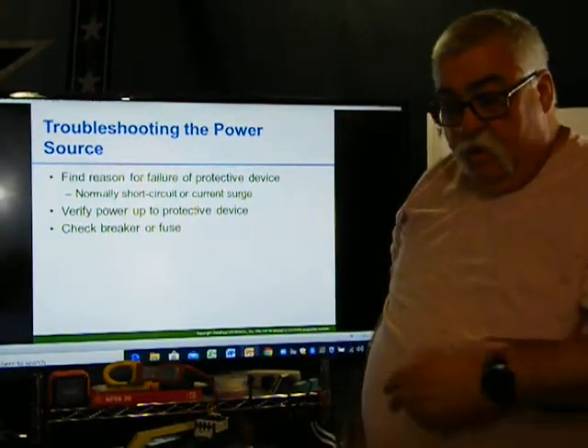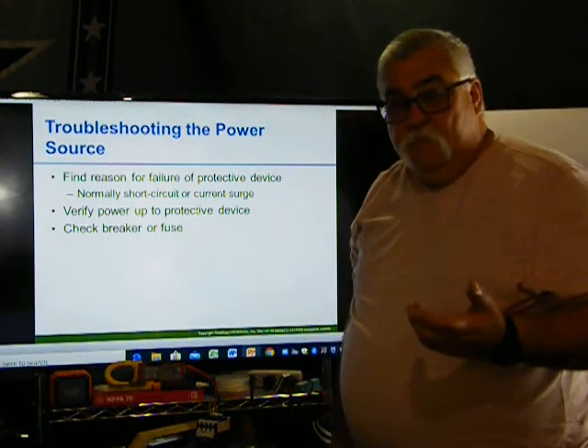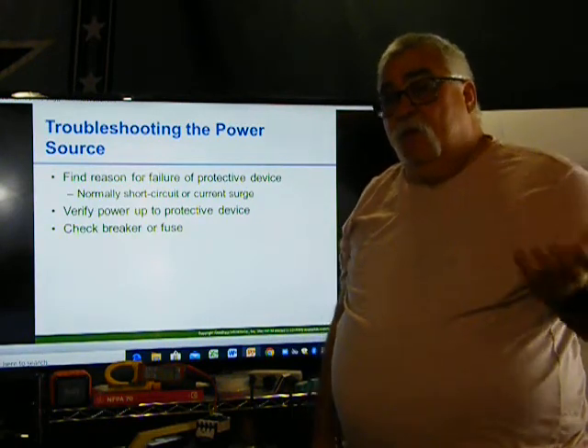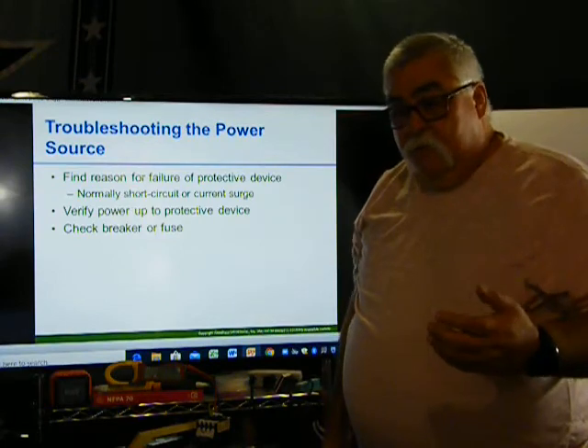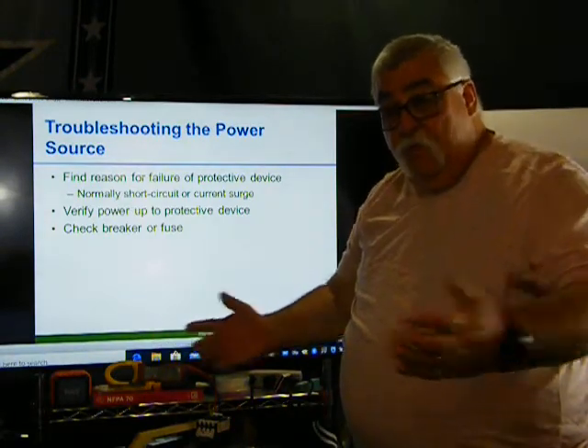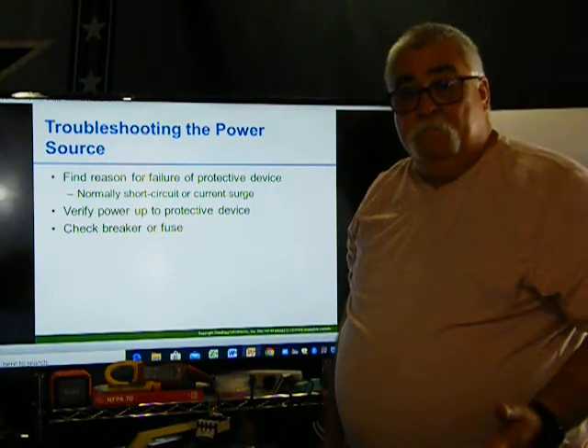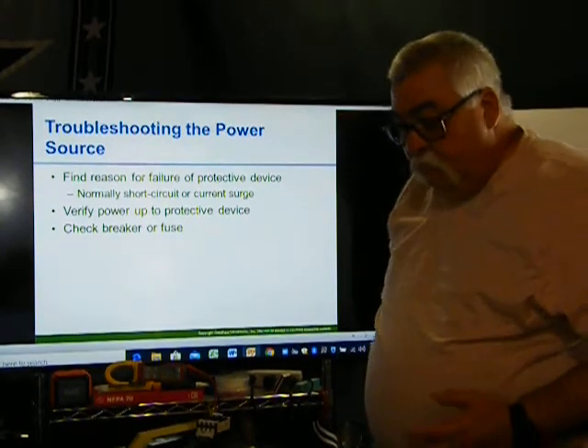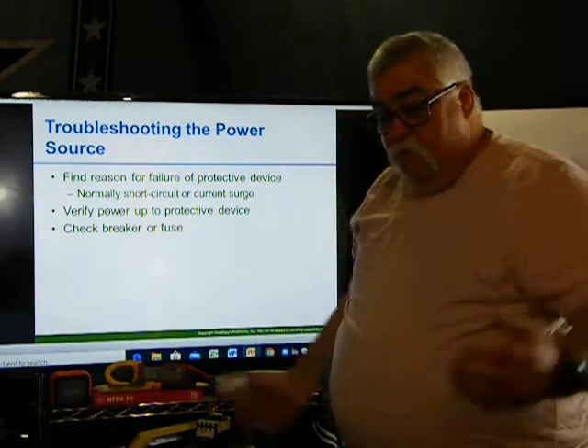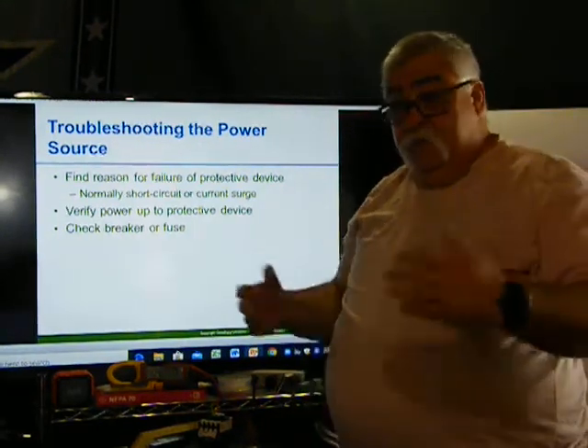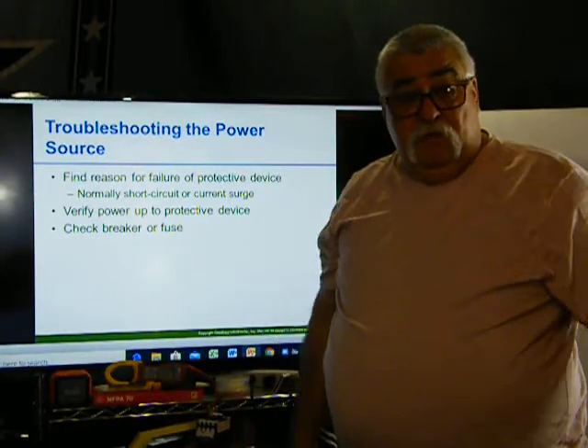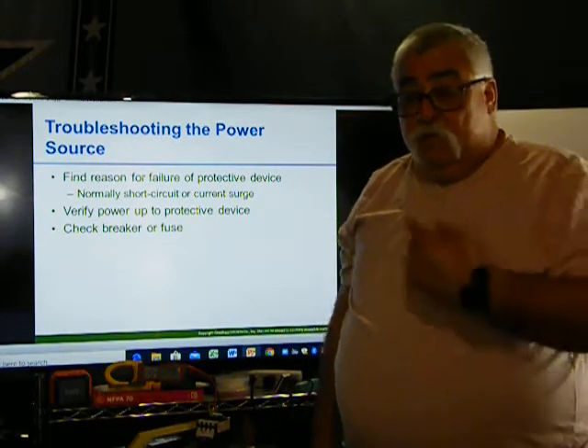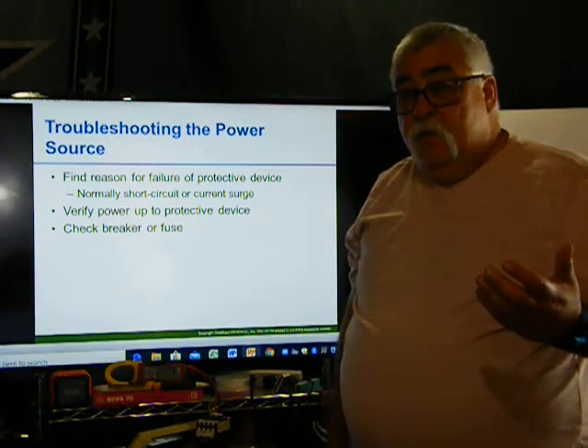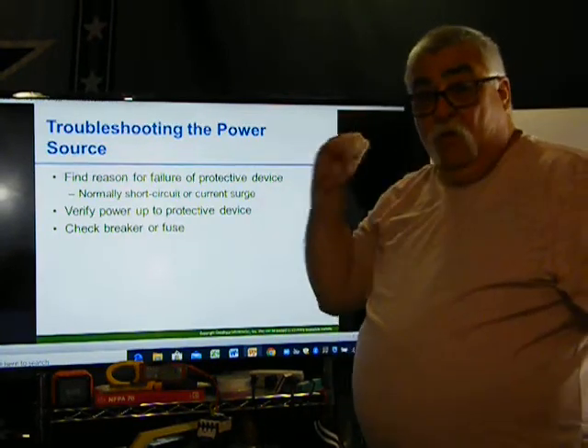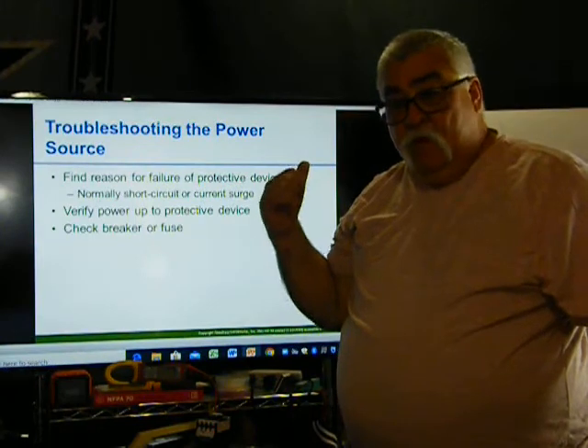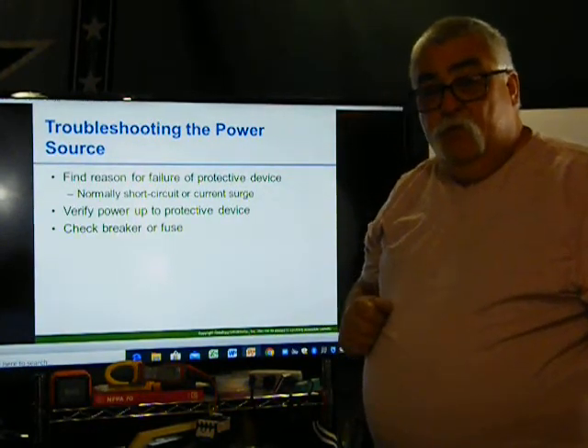Again, I talked about it earlier as a process of elimination. You go back and you have to see what caused it. I use the example of the break room: obviously it was an overload because he turned on too many things at one time. Or a computer room, whatever it may be. You go in there and ask, hey, what happened? I don't know, it just went off. You go back and the breaker's in the trip position. Well, find out what caused that trip first, before you reset.